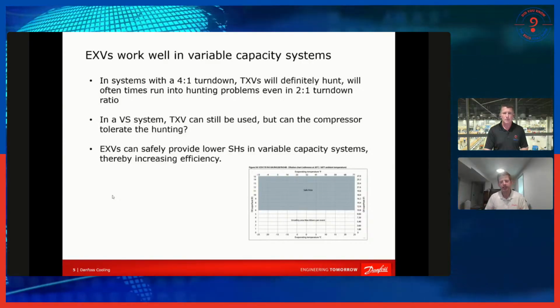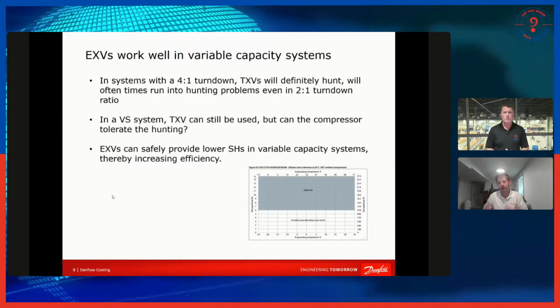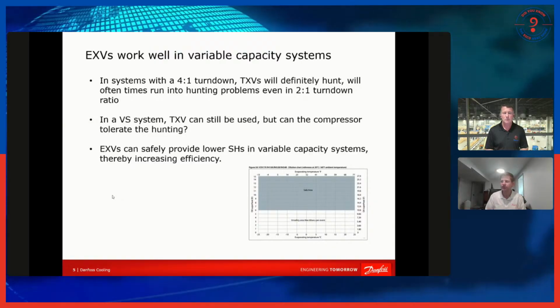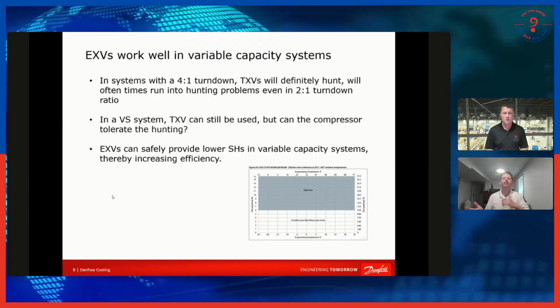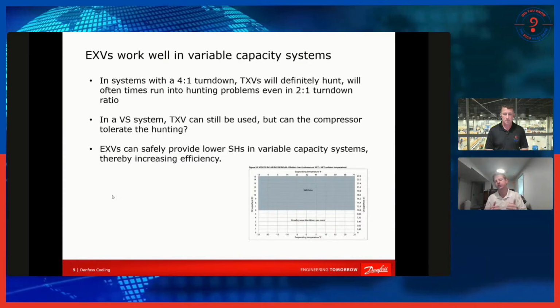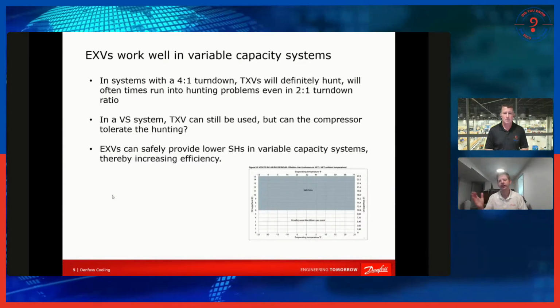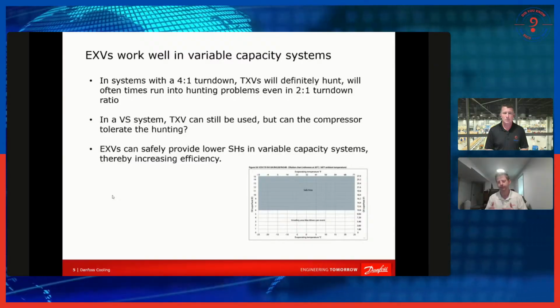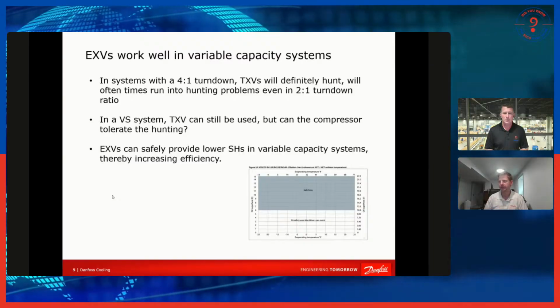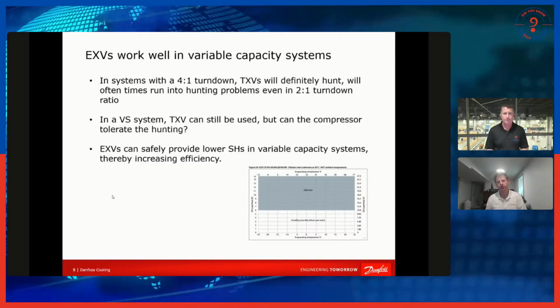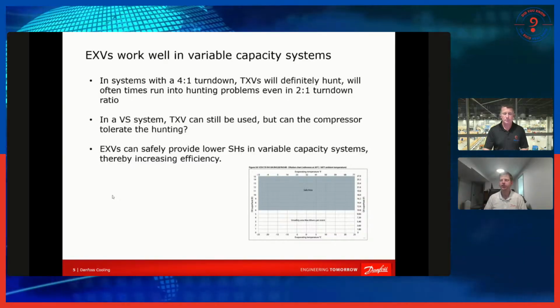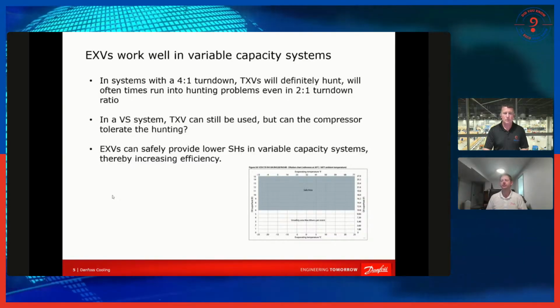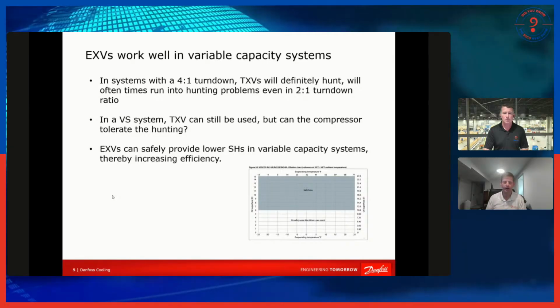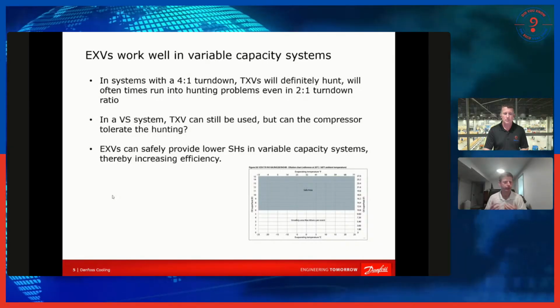Sometimes still, a TXV can be used in those situations, because if you're getting some hunting at your low speeds, if you've got an accumulator, the coil is well designed, maybe the superheat settings set a little bit higher so that it's hunting in a range where you're not flooding back to the compressor, you can still get away with using a TXV, but that's where EXVs can really provide an advantage. EXVs can safely provide lower superheats in variable capacity systems and improve efficiency.